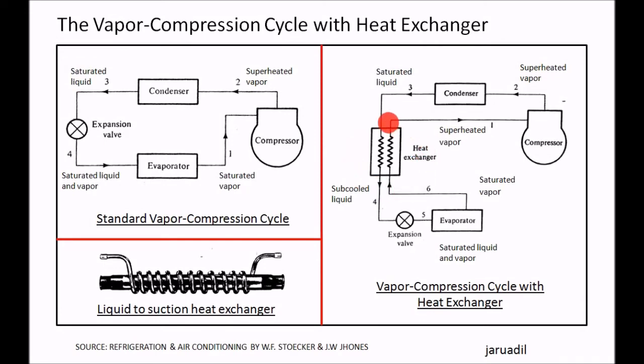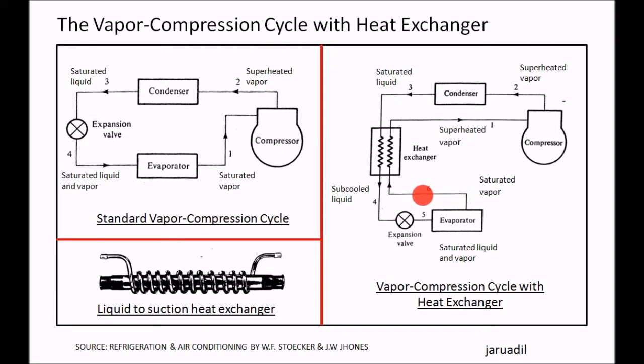The refrigerant from the condenser, upon exiting, will first go to the heat exchanger before going to the expansion valve. Unlike in the basic cycle, where it goes directly to the expansion valve. And the refrigerant from the evaporator, before going to the compressor, will first pass through the heat exchanger.